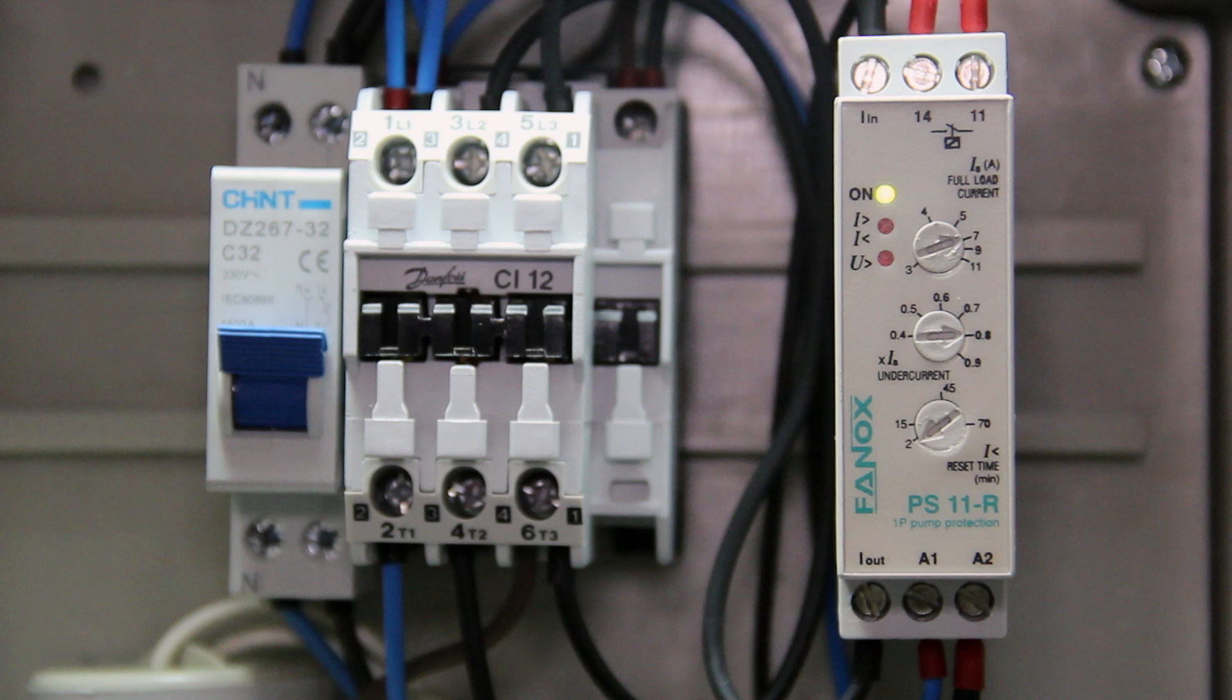It also provides input of the pump supplying cable and output of the pump supplying cable, supplying terminals of the relay itself and tripping contact. For the settings, it contains three potentiometers where we will set the nominal current of the pump, the tripping value because of undercurrent, and the reset time after the undercurrent trip.